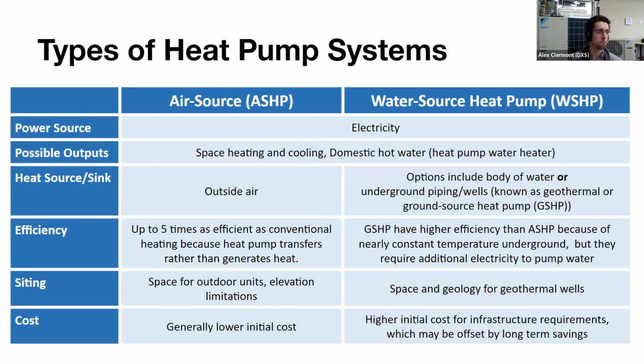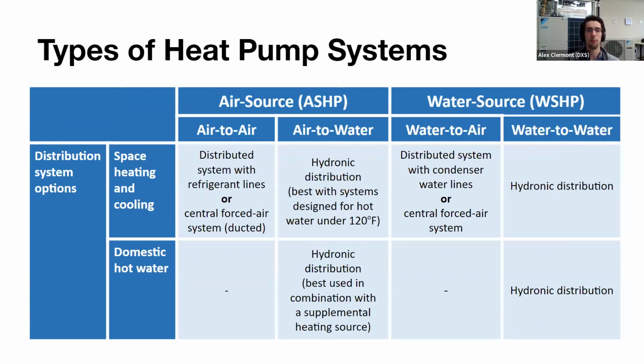In terms of site implications, air source heat pumps require either space on the ground or on the roof. And for water source, they'll usually need a loop. In terms of cost, we're going to dive into a few different options and the different kinds of air source heat pumps, so we'll talk about that in a little bit. This is a big slide, but it's just to let you know that if someone tells you, hey, I have an air source or a water source heat pump, that's only really part of the story, because all this really explains is the heat source or heat sink. And this is a perfect segue into the next slide, which breaks down air source and water source heat pumps even more.